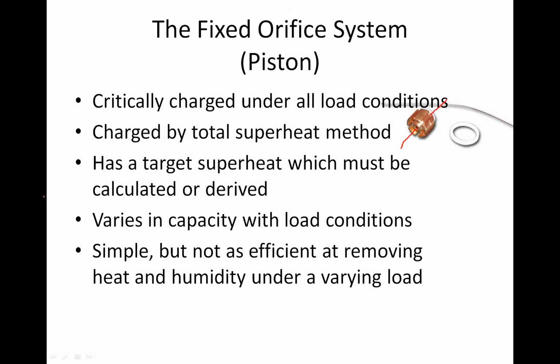It's simple, but not as effective at removing heat and humidity. The metering device itself is a very simple metering device, and it's inexpensive, and that's why manufacturers use it, but it's not as efficient at removing the heat and humidity under the varying load conditions. So, why do we use a fixed orifice? Cost, inexpensive. Why do we use a TXV? Efficiency and better load control.